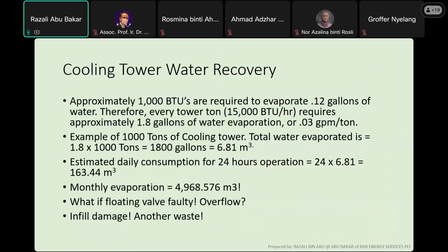The cooling tower water usage, based on the evaporation rate, is like 0.1% to 0.2%. You can see that the bigger the chillers, the bigger the cooling tower capacity in tons. So imagine with 1,000 tons of cooling tower, the monthly evaporation is 4,968 meter cube. This shopping complex is also running about 1,000 to 1,200 RT, meaning that almost half of their water usage actually comes from the chiller plant because of water evaporation.